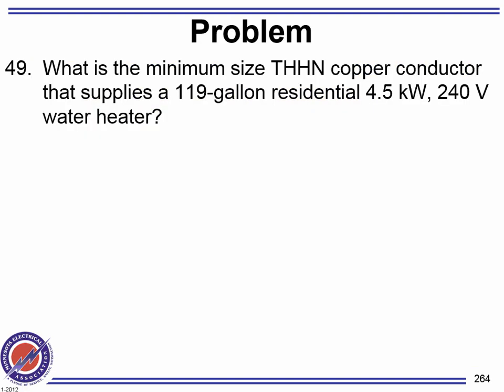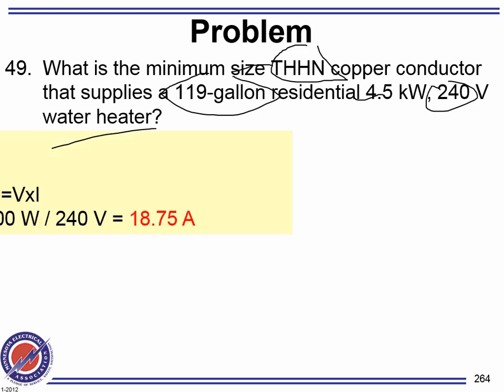What's the minimum size THHN copper that supplies a 119 gallon residential 4.5 kW 240 volt water heater? If you look at the 119 gallon residential, this will tell you guys water heaters are considered what? Continuous load. So then that's it. Find the amps, multiply by 1.25, and size the conductors. Do we size conductors based on kW, kVA, or based on amps? Amps. But if we have the kW, what do we need to do? Find amps. Okay, there you go.